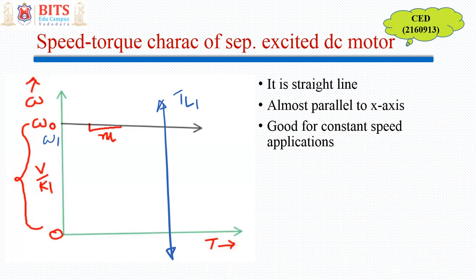Now suppose suddenly the load reduces. The new speed ω2 is almost very near to ω1, so there is not much variation. ω2 approximately equals ω1. For constant speed applications like lifts, escalators, or conveyor belts where load variation occurs but you don't want speed to vary much, this type of characteristic is very useful.